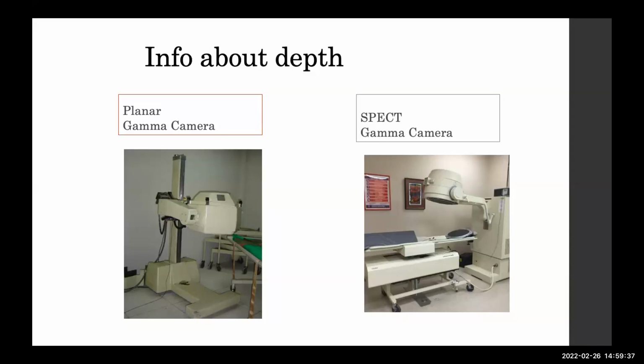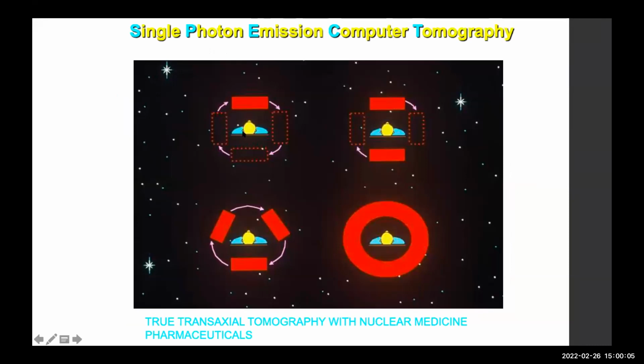a move-and-stop mode, where at each stop, at each angle, the camera detector stops, gathers the radiation events coming from the patient, and then moves to another angle. It takes events for a few seconds, then moves to another angle. So around the 360 degrees of the patient, it acquires the data at different angulations and makes tomographic images. You can see this very simple picture. Here it is a single head gamma camera. The patient is lying down. The detector is moving 360 degrees, from anterior to lateral, coming posterior, and then right lateral, and then again coming anterior.